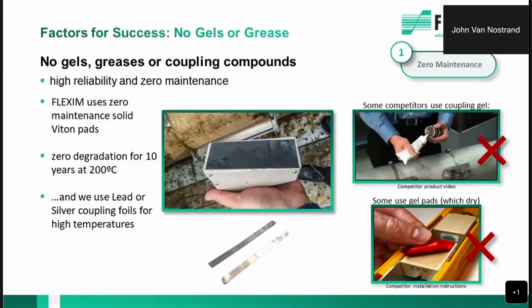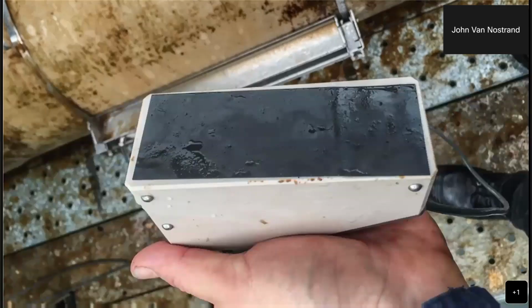First of all, the coupling pad. So we have zero maintenance once you install it. And the reason for that is that we use a coupling pad rather than a traditional grease. If you've ever used ultrasonics before, you know you use a grease on the face of the transducer. And over time, that grease actually goes away. It washes out or it gets crusty. The coupling pad doesn't do that. This is an up-close picture of what it looks like. I typically use just a slight bead of grease there on the coupling pad behind it in order to hold it in place so you can slide it right into the track. And that's what makes it maintenance free.